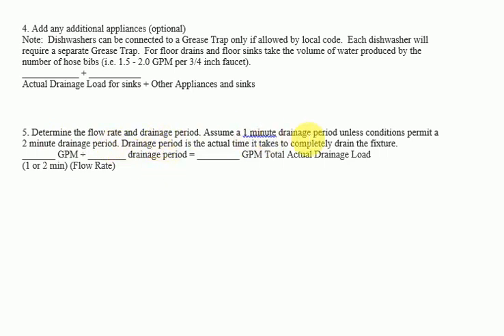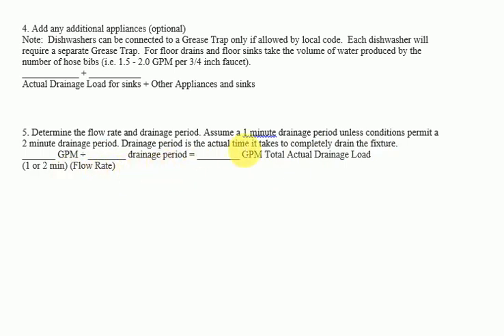Step 5 — Determine the flow rate and drainage period: Assume a 1-minute drainage period unless conditions permit a 2-minute drainage period. The drainage period is the actual time it takes to completely drain the fixture. Divide total GPM by the drainage period (1 or 2 minutes) to get the total actual drainage load in GPM.